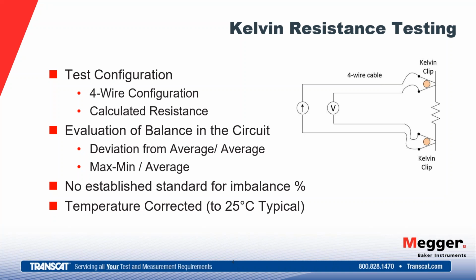The first one is deviation from average. So we take whatever is the most deviation from average of the 3 values, divide that by the average, and we get an imbalance calculation there. Then we're going to compare it to a threshold. So there's 2 ways, again, as I said, to evaluate this imbalance. The second method is max minus min. Divide that by the average, and that also would give us an imbalance calculation.